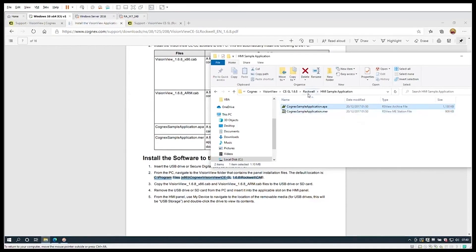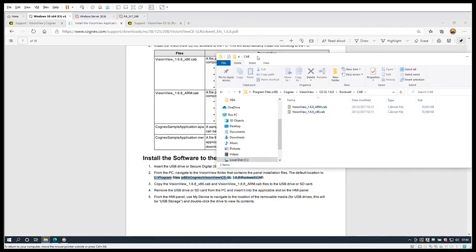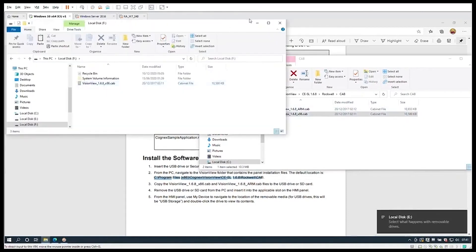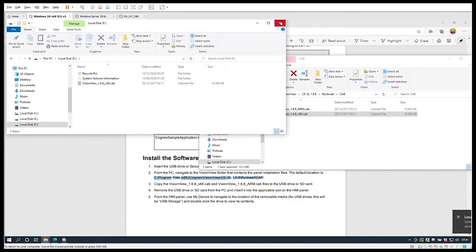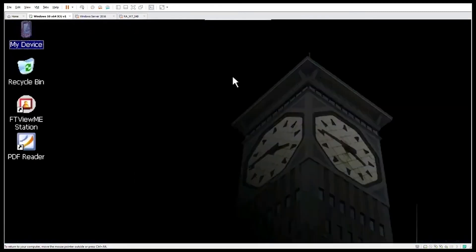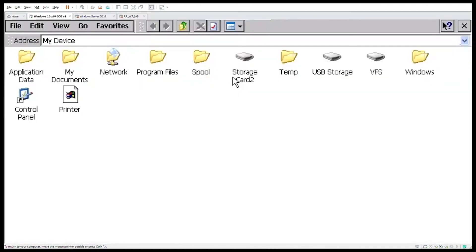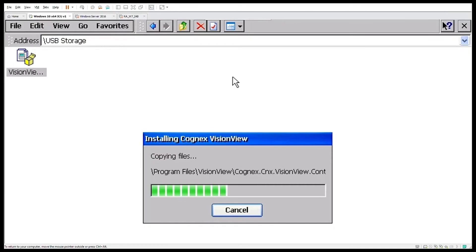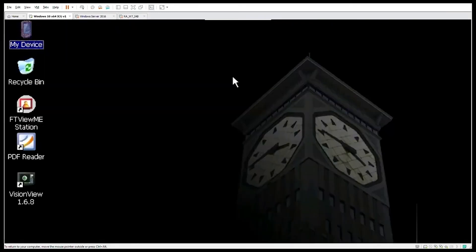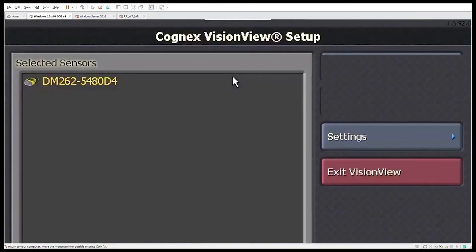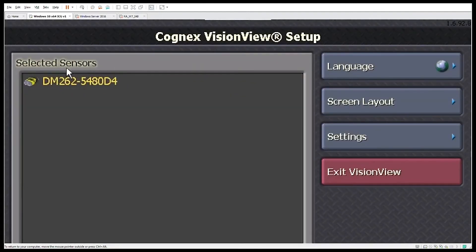You should be familiar with restoring an APA file back to the FactoryTalk View software. We're interested in the cab files, and we're using the PanelView Plus 6, which is the x86 cab file, copied onto a USB stick. Plug the USB stick into the HMI and install the Cognex software — you will need desktop access onto the HMI to install this. You can see VisionView is now installed on the desktop and you can run it as an application. It will automatically pick up Cognex devices it is compatible with, including barcode readers.